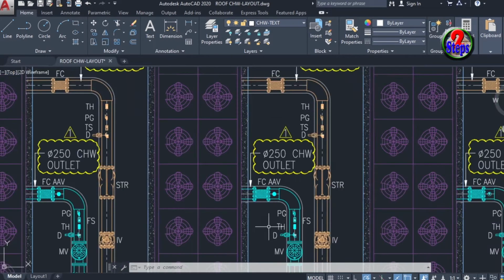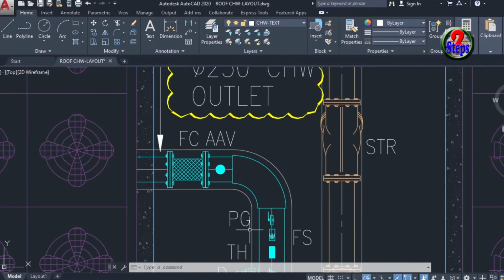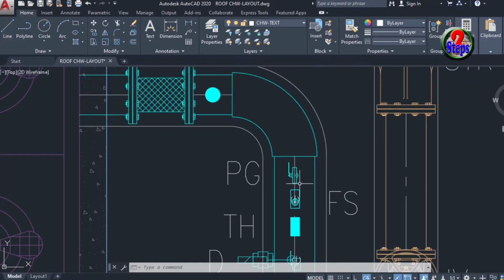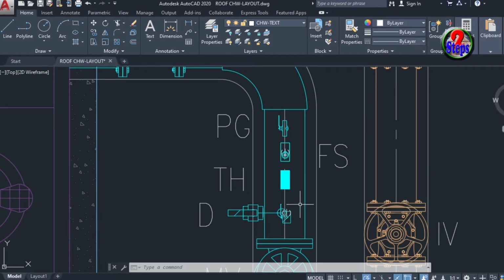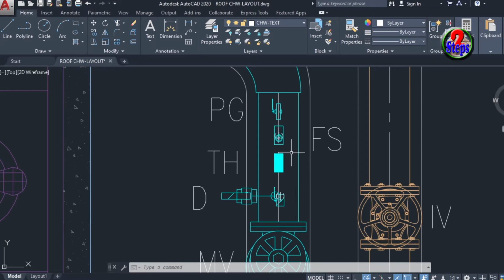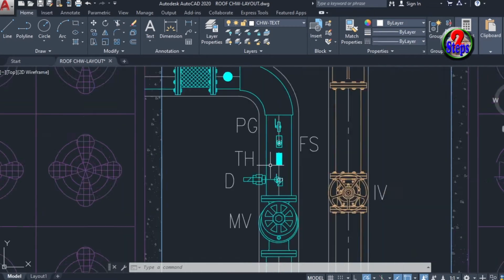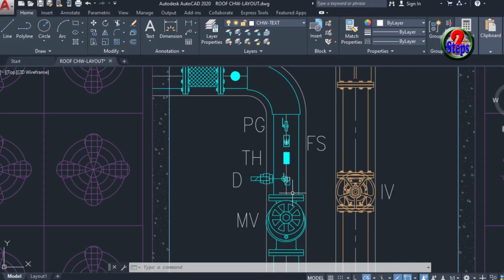Here also have one pressure gauge in the outlet line, same as the inlet line. After that, the outlet pipe has one more point for a flow switch. In the drawing, the symbol is FS. It is connected to the BMS to calculate the water flow inside the pipe. Here also have a thermostat point and drain point, same as the inlet pipe.